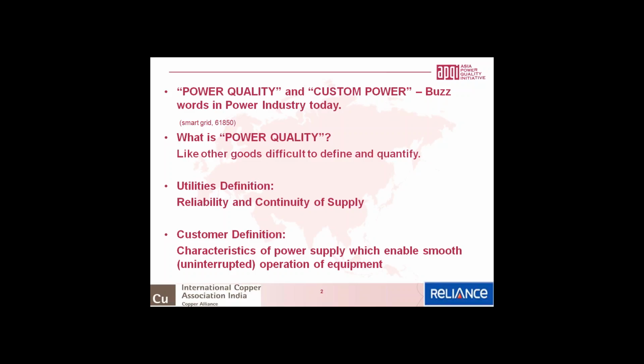Power quality and custom power, I think these are the two buzzwords spoken very frequently in the power industry. Of course, it depends on the utility or the supply. You would not expect utilities to supply power to millions of customers like a UPS. There will be faults in power systems. Whenever there is a fault, there will be voltage dips due to various reasons, and there could be interruptions due to tripping of generators and networks. The customer's definition could be that the characteristic of the power supply should enable smooth, uninterrupted operation of the equipment.